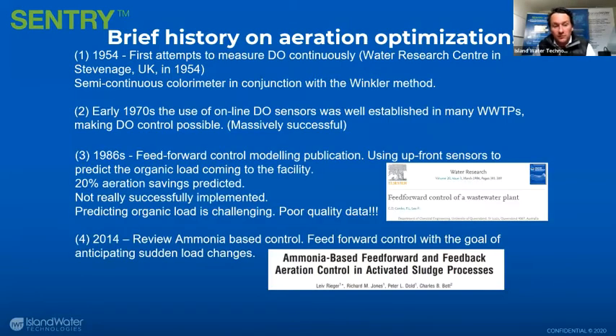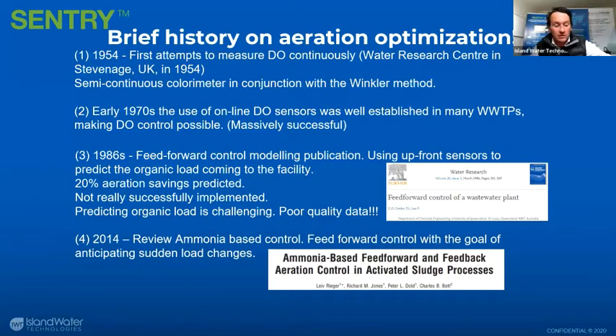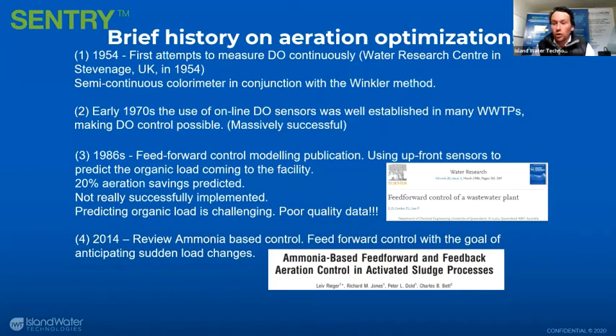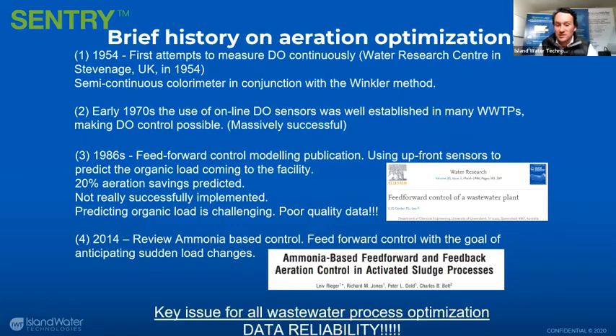But that's not where it stops. Going forward, whether it's the 80s or more recently, people have looked at feed-forward opportunities — understanding directly the quantity of carbon in the wastewater to predict what's coming into aeration basins. More recently, looking at ammonia-based control, whether feed-forward ammonia-based control, using that information to understand the disturbance and better understand fluctuations in load as it comes into the plant. All of it comes back to measuring and data. If you have good data, you can make smart decisions and save money.